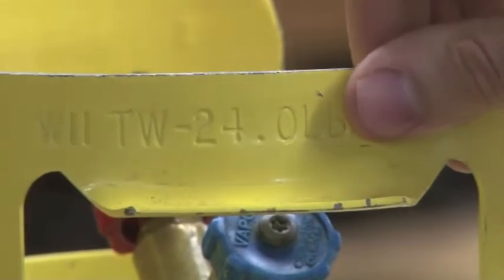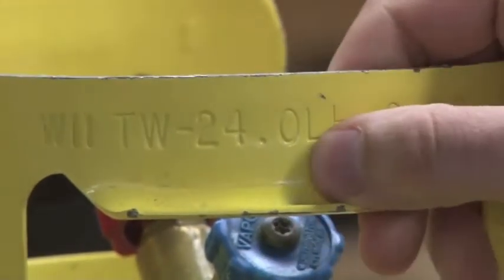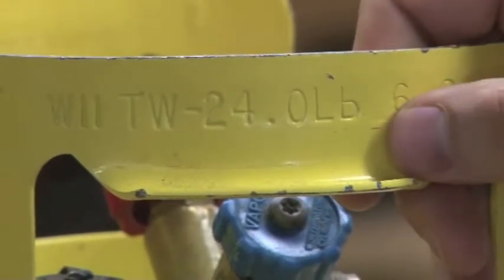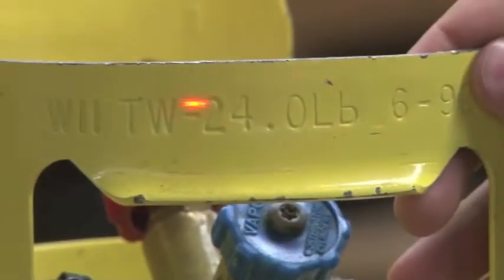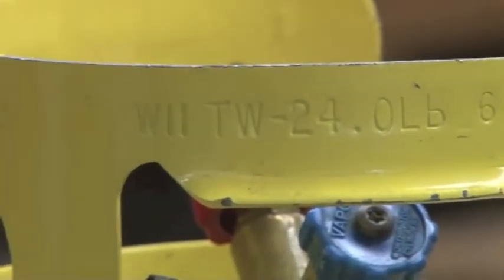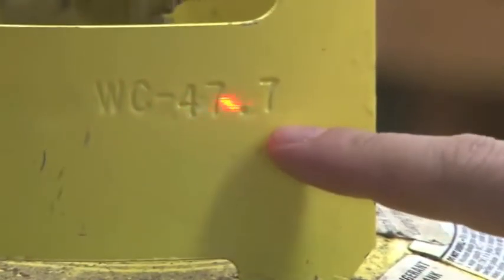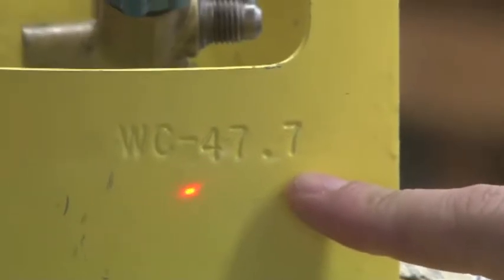That is what the jug weighs empty. This is a 50-pound cylinder, allowed to 80 percent, so we can put in 40 pounds. It weighs 24 pounds empty, so 64 pounds is the absolute max we'd go. And for our hydrostatic test, the water capacity is 47.7 — that's going to be on every approved jug.